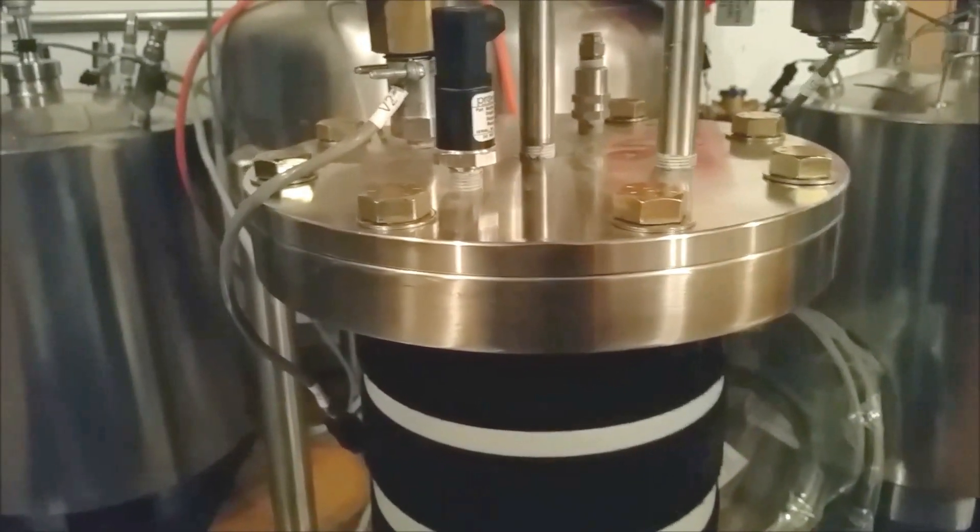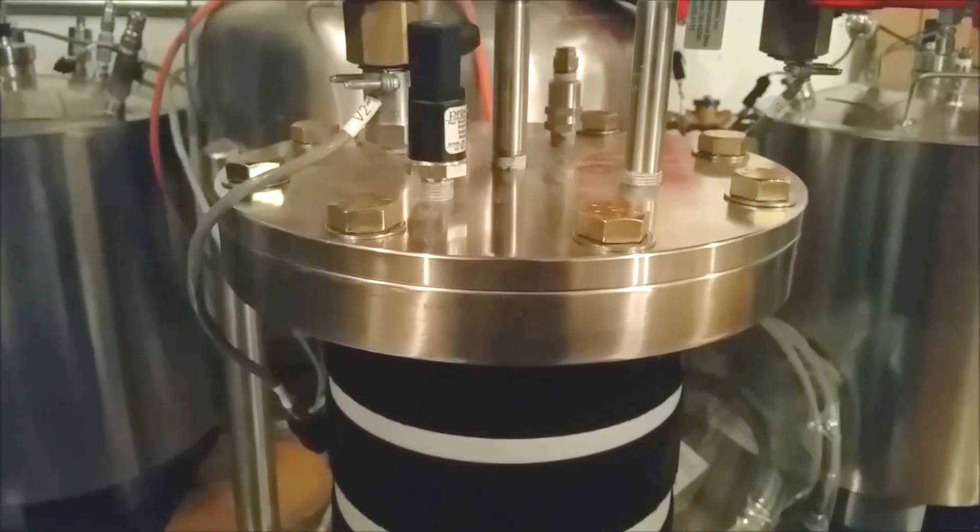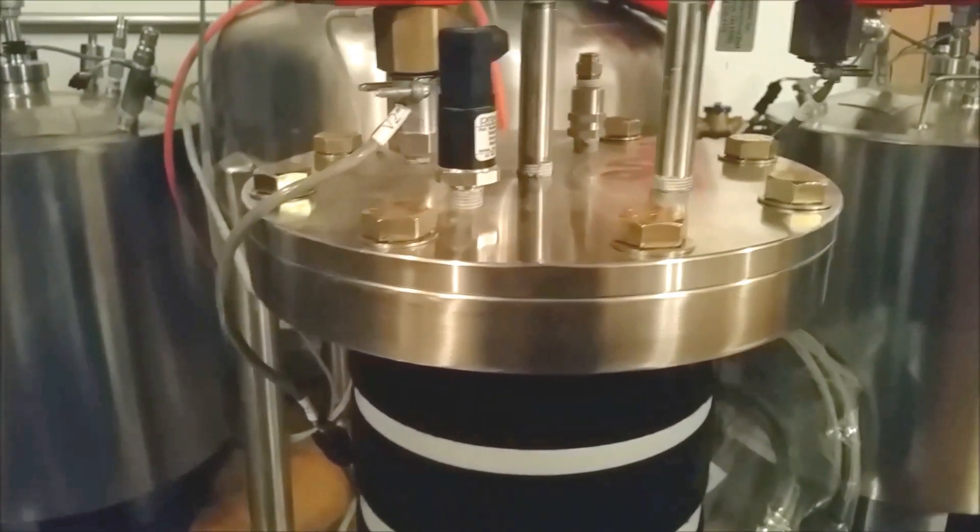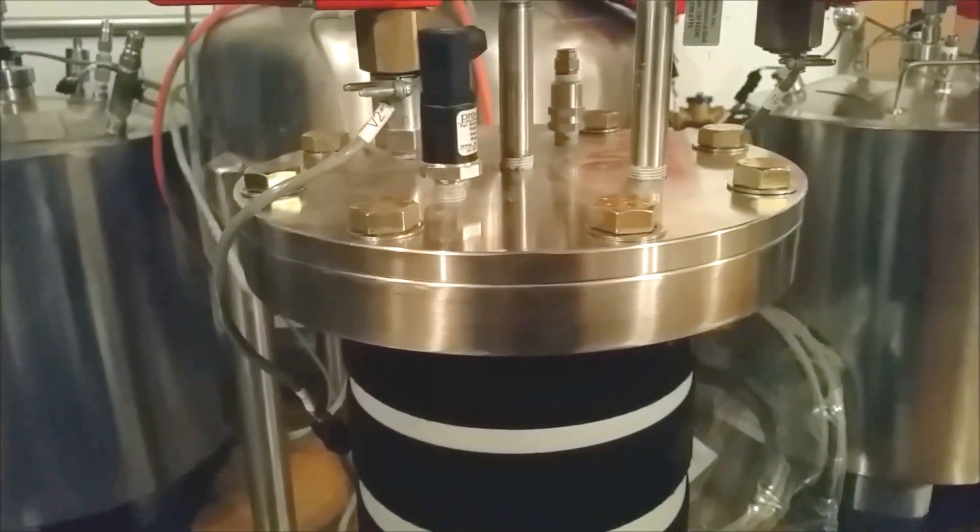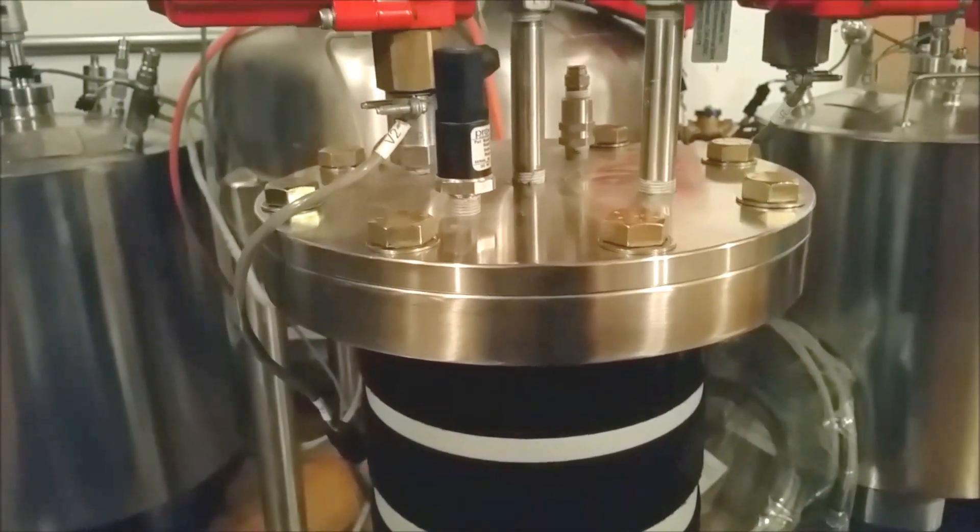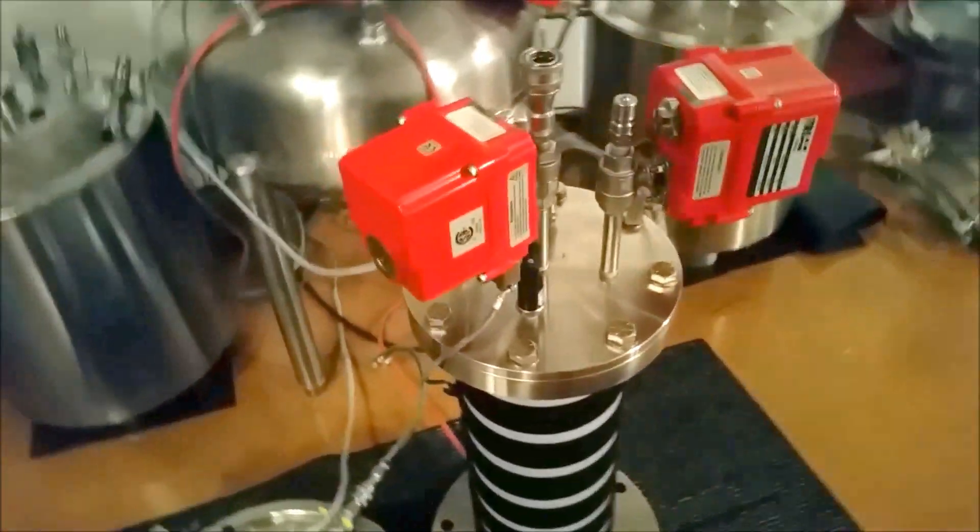The bolts are nice and snug. What you're trying to do is prevent any gap from being between these two parts. When the bolts tighten down, you'll feel a definite stop and you'll know that the two parts have mated together. Then you just snug up the bolts. There's a torquing sequence, but it really doesn't matter because once you get this up on the extractor tank and you've resealed this lid onto this column, you're going to have to pressure check it anyway. Once you bring it up to pressure and discover there's a leak, you can always just tighten it up then or remount the lid, but you're not going to have that problem—it's pretty cut and dry.